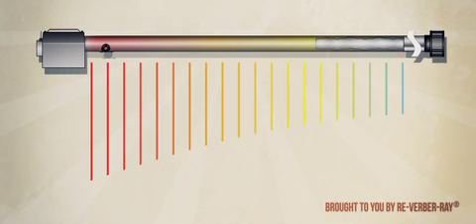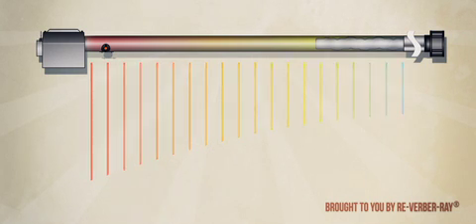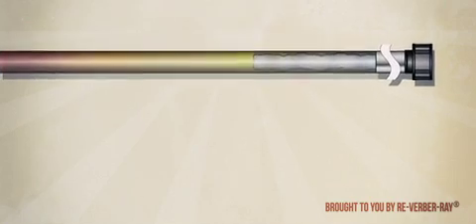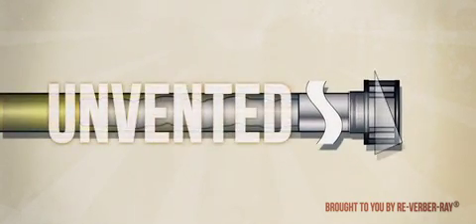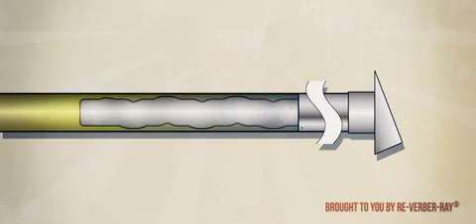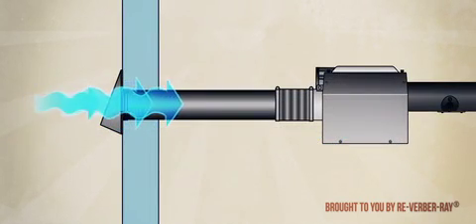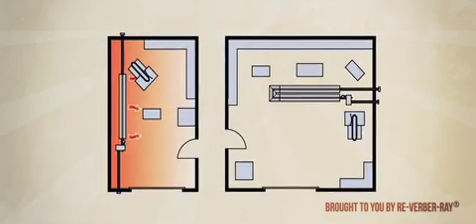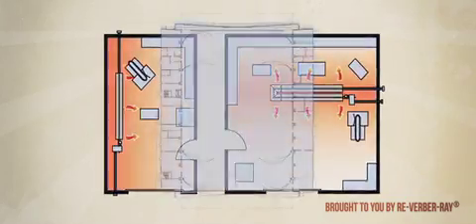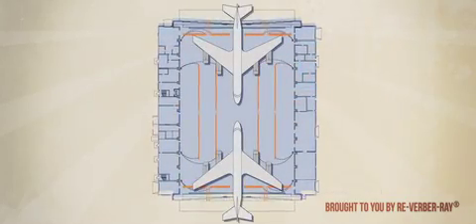This results in a temperature differential, which should be highly considered during the design phase. Low-intensity heaters can be installed either vented or unvented and may bring in outside air for combustion if necessary. They are typically installed in applications where total area heat is required or can be configured to conform to the expectations of the space, providing maximum flexibility in the placement of heaters.